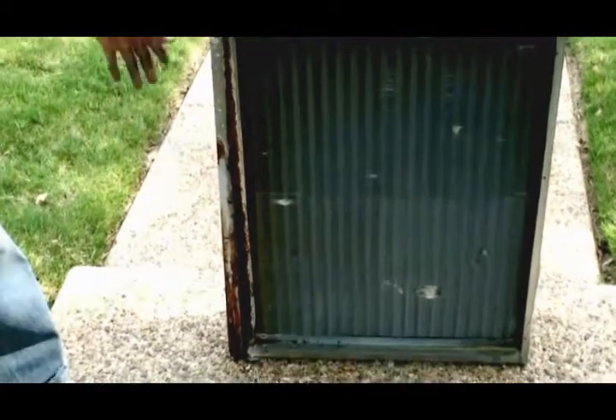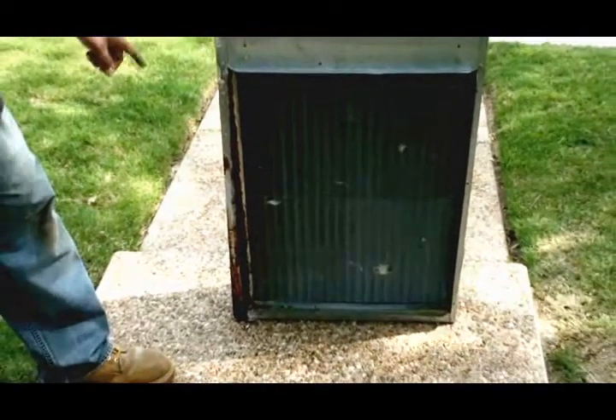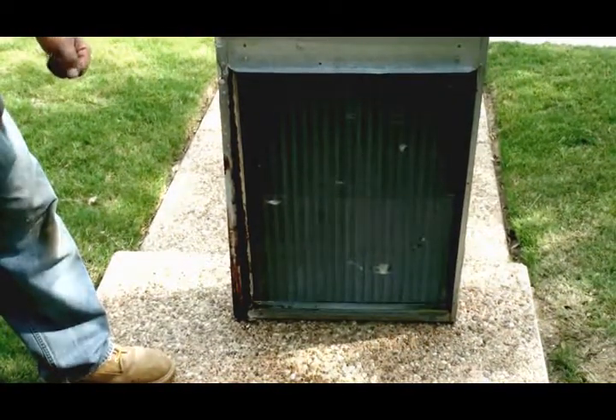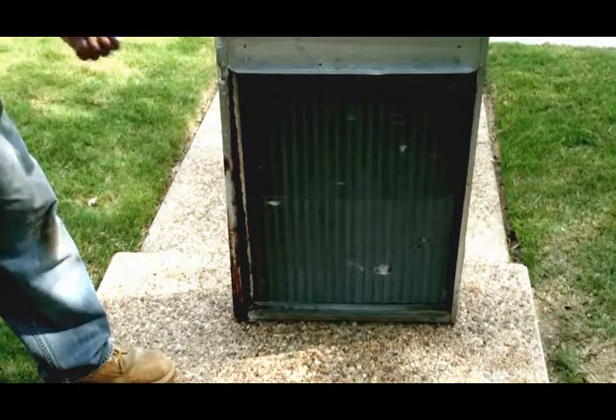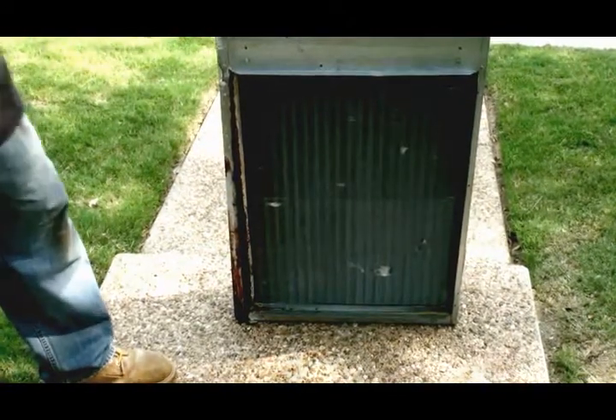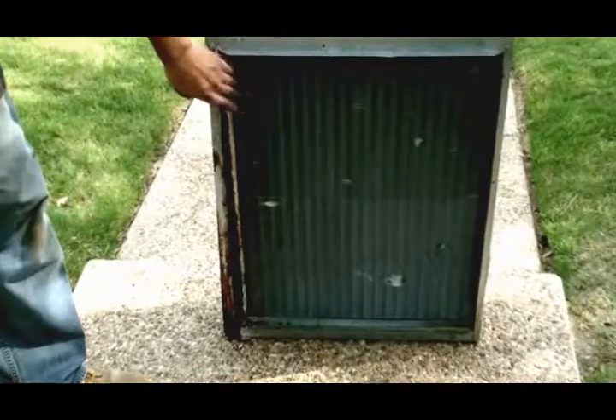and that allows for water to drain out and sometimes overflow into your plenums and stuff like that, and you'll have continuous overflow on your secondary drain line, which is the one that goes to the outdoor drains where you can see anything leaking or anything like that. That's what we advise homeowners to do, is just to pay attention to something like that. When you've got secondary drain lines draining water continuously, you usually have either a problem with your main drain or simply the coil's already rotted out.